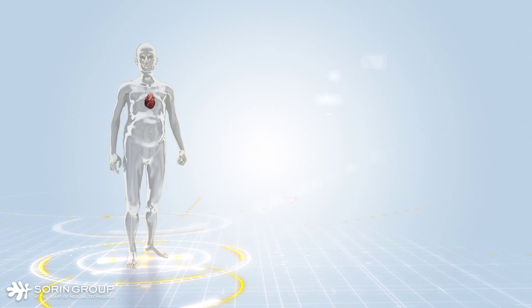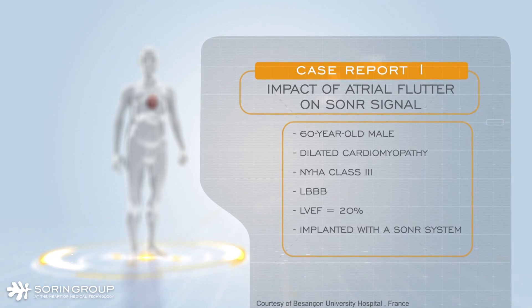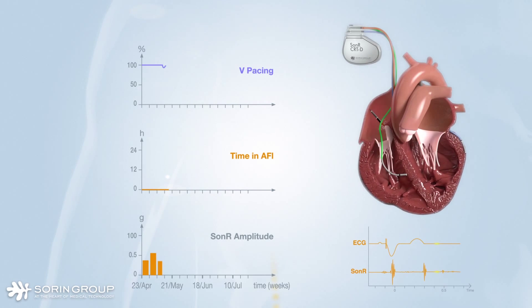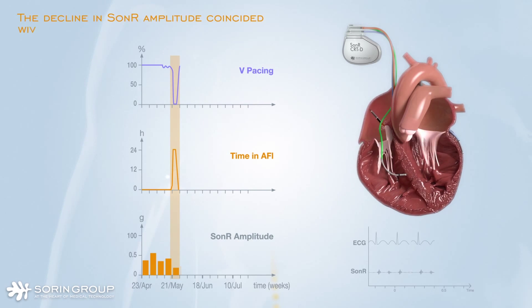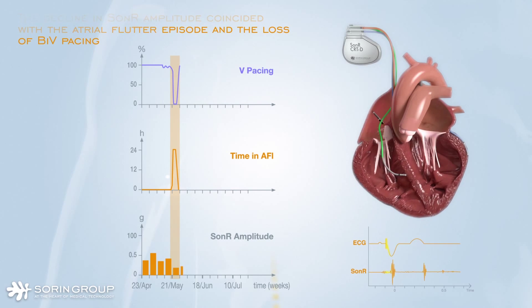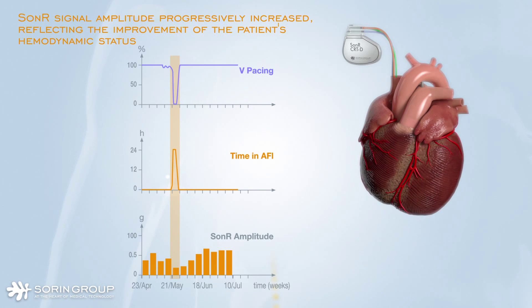Two real-life case reports illustrate the benefits of SonR hemodynamic measurements. In the first case, the SonR signal reflected the hemodynamic status of the patient. Three months after implantation of a SonR system, the patient was hospitalized for fatigue and his ECG showed atrial flutter. The decline in SonR amplitude coincided with the atrial flutter episode and the loss of BiV pacing. Sinus rhythm was restored after 48 hours of treatment with amiodarone, and SonR signal amplitude progressively increased, reflecting improvement of the patient's hemodynamic status.